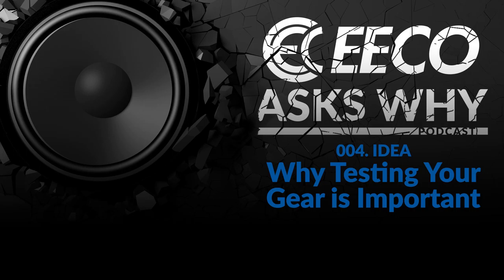And you'll actually trip the breaker. You'll have to reset the breaker and run it through its testing. It's secondary injection. It's quick. It validates the electrical system to a point, and it's typically satisfactory. It's good enough to know that the breaker is going to function properly.